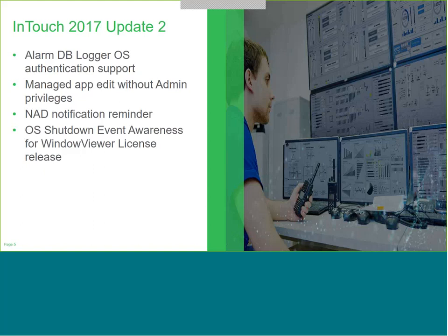You can now do, in terms of managed apps, the integrated development environment. You can still develop InTouch inside of there as a standalone application, but if you want to use things like ArchestrA graphics, and perhaps you do want to manage it through that integrated development environment, so you want to push out InTouch applications across the network from one central location, you can now access that application without admin privileges. We'd always say install the software with local admin on that machine, but again, they're trying to remove this reliance on administrative privileges to improve the security of the system.